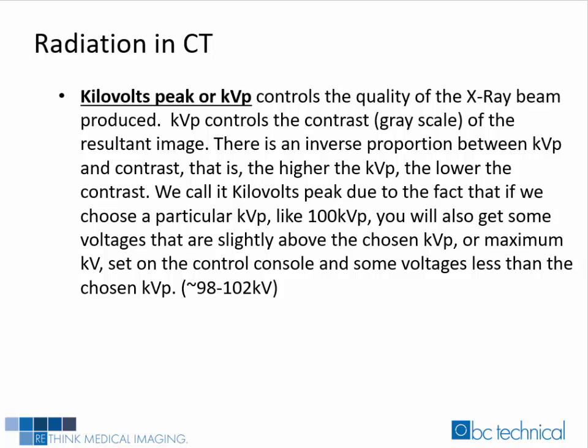Kilovolts peak, or kVp, controls the quality of the X-ray beam produced. kVp controls the contrast, or grayscale, of the resultant image. There is an inverse proportion between kVp and contrast. That is, the higher the kVp, the lower the contrast.